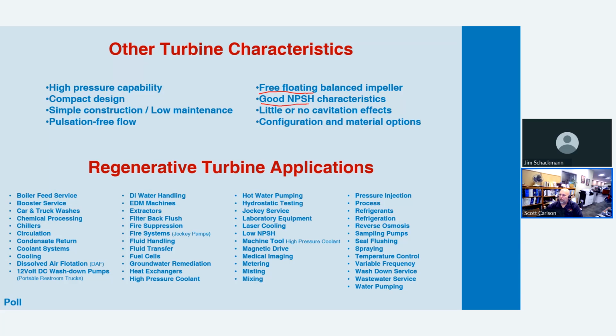Another characteristic here is the NPSH characteristics, because all of the work of the fluid is being done on the outside of the impeller. Any vapor that does form in it can exit out of the pump immediately and doesn't have time to accumulate like it would in the eye of a centrifugal impeller. So there is little to no cavitation with regenerative turbine pumps. And we do have several different materials, which we can go over later.